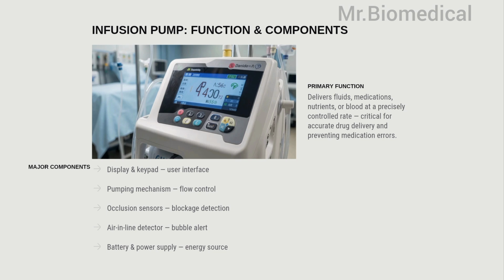The display keypad allows the user to enter the settings and monitor operation. The pumping mechanism physically controls the movement of the fluid. The occlusion sensor detects blockages in the infusion line. The air-in-line detector identifies air bubbles that could enter the patient's bloodstream. The battery and power supply provide energy to the device during operation. When any of these components fail, the pump generates an alarm or may stop functioning altogether.